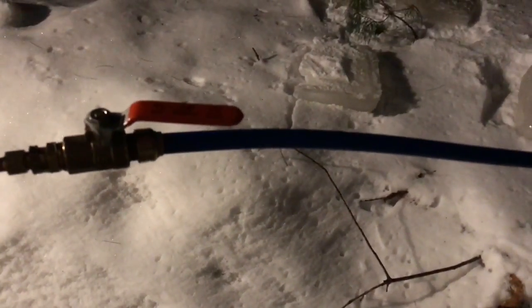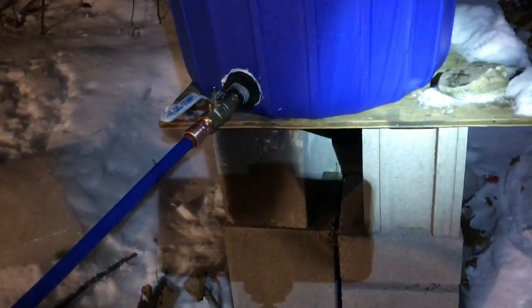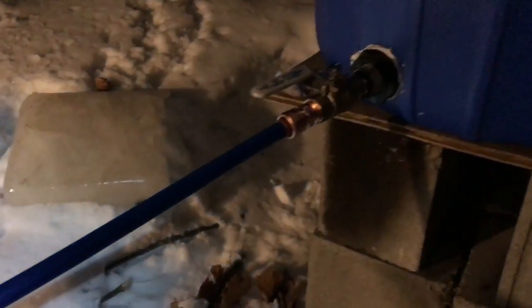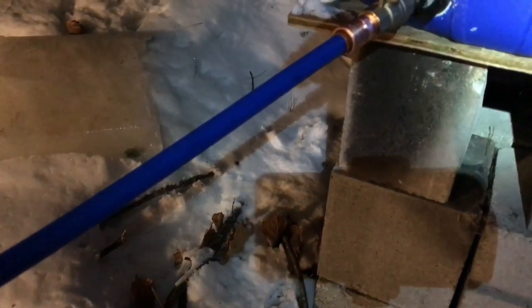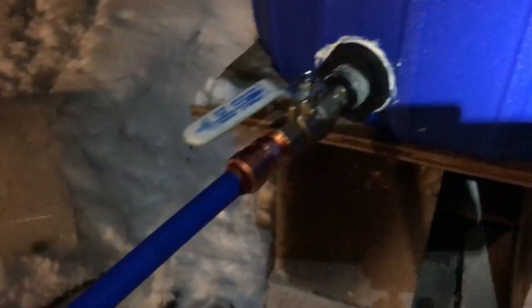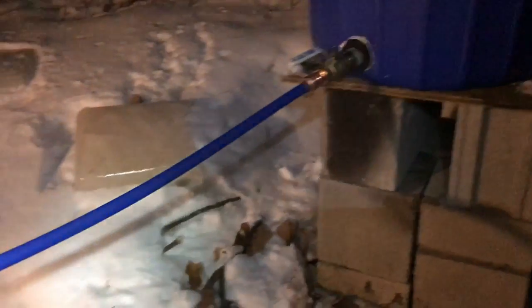While it was running earlier I had to stop it. I had ice from this joint all the way down to this joint — let me turn my headlamp on so you can see. I took this one off and I couldn't even blow into the pipe, so I had to heat that up until it ran through. Then this joint had ice in it — I had to use my torch to heat that up until it came through. I slowly heated this plastic section with the torch, which made me nervous, but it came out okay. I finally closed the valve, opened it back up, took the pipe off — that had frozen too. With all the plastic here I had to be careful, but I was finally able to get it running again.